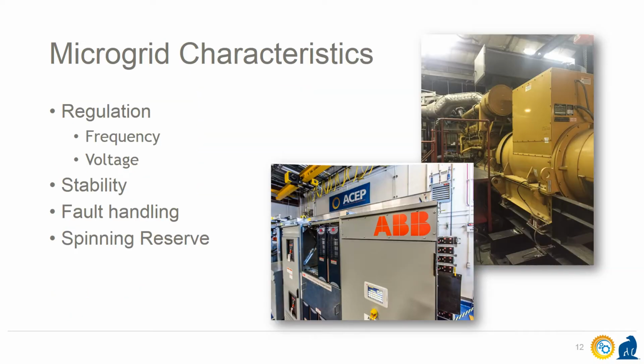In addition to the components of a microgrid I've discussed, there are several other very important characteristics that must be accounted for. Loads are rated and generally expect to operate at a certain voltage and frequency. The grid-forming source that provides the backbone of a microgrid must be able to maintain and regulate these values, otherwise some loads may be damaged. Typically, a diesel generator, hydroelectric turbine, or high-temperature Rankine cycle generator will form and regulate the grid, although certain types of grid-forming inverters are capable of doing so as well.